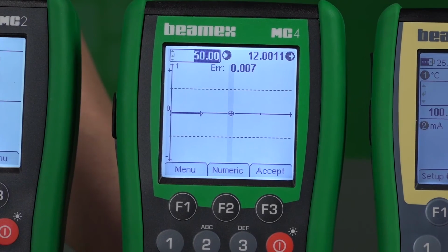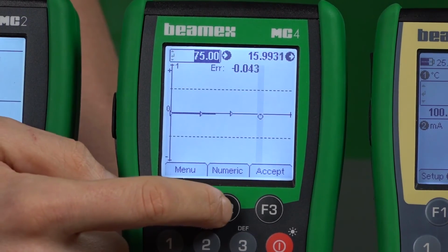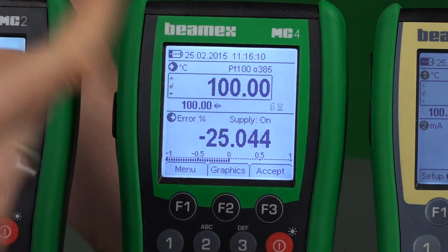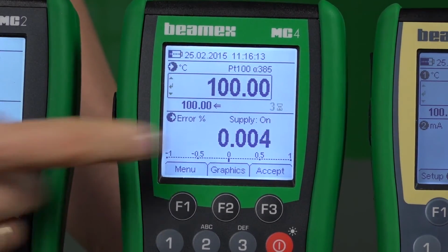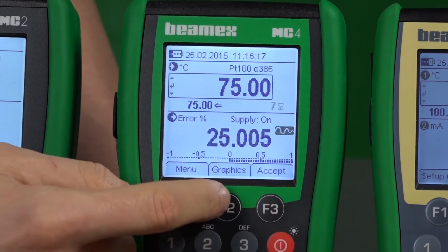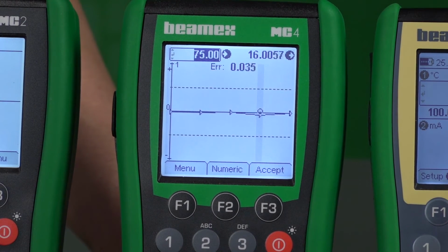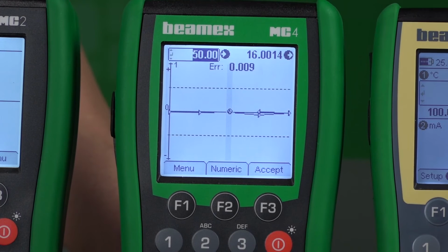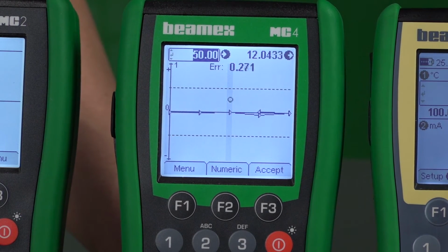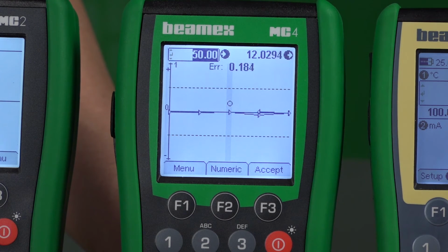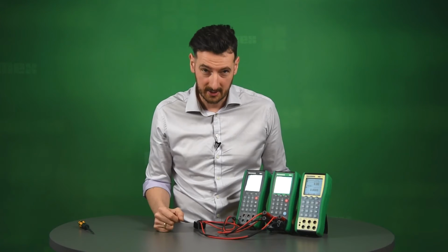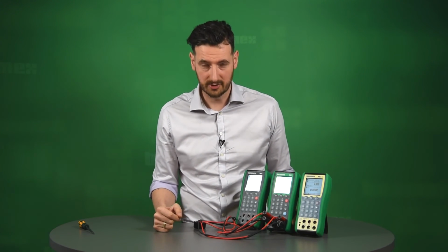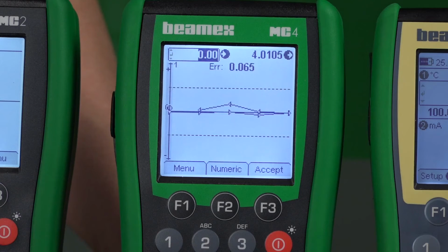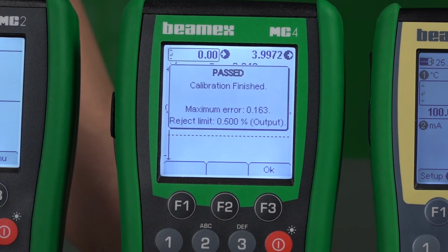You can see right now the calibrator is going through those 5 steps up. This is the graph. If we click numeric here, you can see the same calibration happening at the same time. You can see right now we simulate 100 and you can see the direct error response and you can see the graph. We can go back to the graphical representation of this and we just wait for it to complete the calibration. It looks as if we are well in tolerance, so the calibration is looking good. Okay, so it looks as if we passed the calibration.